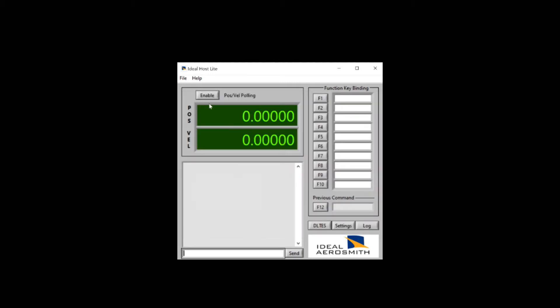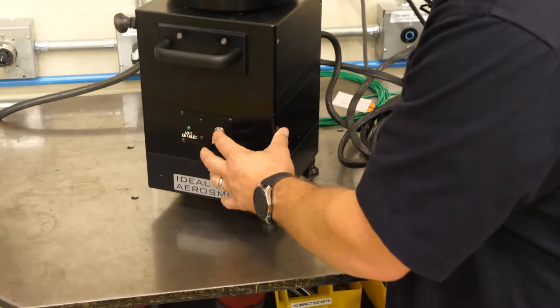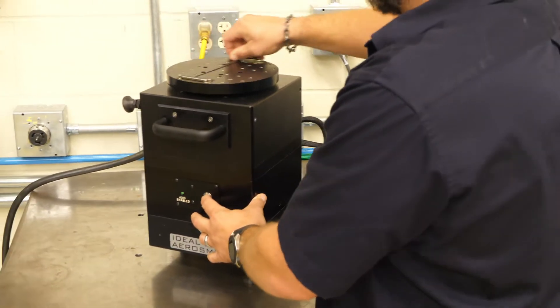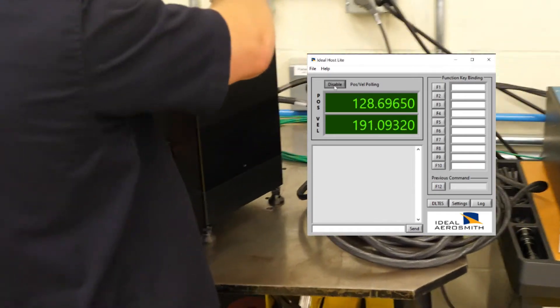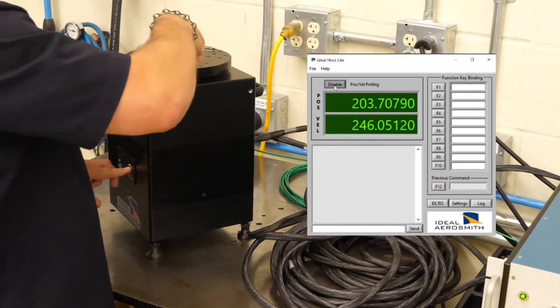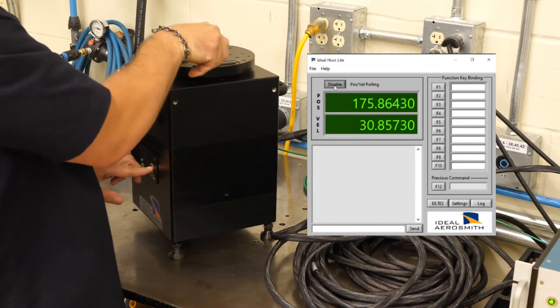And we will enable polling to see that we have some position. To make sure that we have actual feedback, we will go over to the rate table. We'll press the brake release button on the front of the rate table, rotate by hand to see that the brake is released. And we'll watch the display on our host to see that we have position feedback changing as we rotate, which we do.